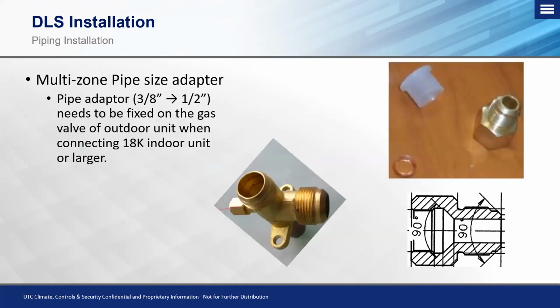Now on our multi-zone systems, the size of our indoor unit is going to determine the size of our suction line and also our mixed phase line. Now, on the suction line, we have adapter fittings that will hook on there. In this case, it'll go from a 3/8 suction up to a 1/2 inch suction on larger indoor units. This is going to be for indoor units that are 18,000 BTUs or larger, which is when we need this multi-zone piping adapter fitting to bring the suction line size up to 1/2 inch.